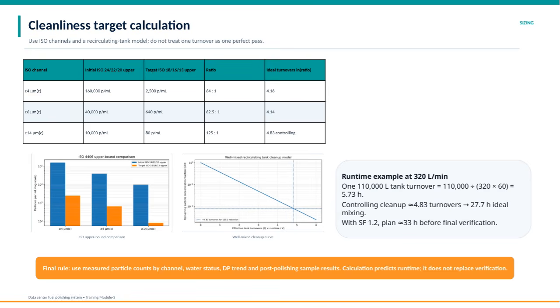Looking at the table, we see initial particle counts and target levels for different ISO sizes. For example, for particles sized 4 microns and above, the initial count is 160,000 particles per milliliter, and the target is 2,500 particles per milliliter, which corresponds to a ratio of 64:1. The ideal number of turnovers needed for this reduction is about 4.16, calculated using the natural logarithm of the ratio.